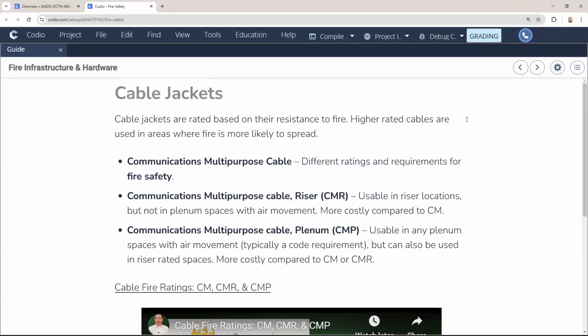Okay, so we will focus now on some of the aspects that are related to data centers more than any other location, which is cables. We will discuss some of the components in IT systems that cause the fire to spread within a data center. And one of the main ways for fire to spread is the jackets of the cables. These jackets are made of PVC, and this PVC is combustible and it can spread fire.